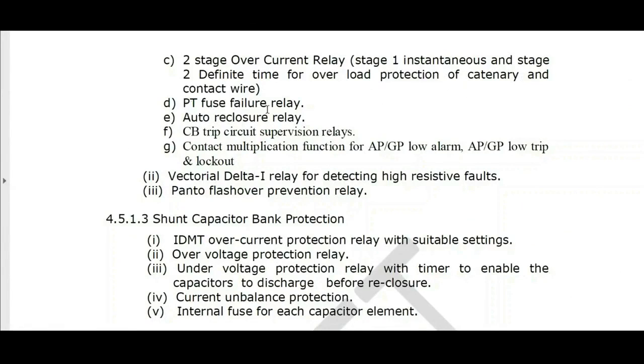So next one, PT fuse failure. What is PT fuse failure? We already saw in the impedance section, Z is equal to V by I, which means voltage divided by current. The voltage which is connected to the relay is connected through a PT, connected through a fuse. This fuse, if it blows out, what will happen? The relay will not read any voltage. If there is no voltage, what happens? Z is equal to V by I. V becomes 0. That means Z becomes 0.